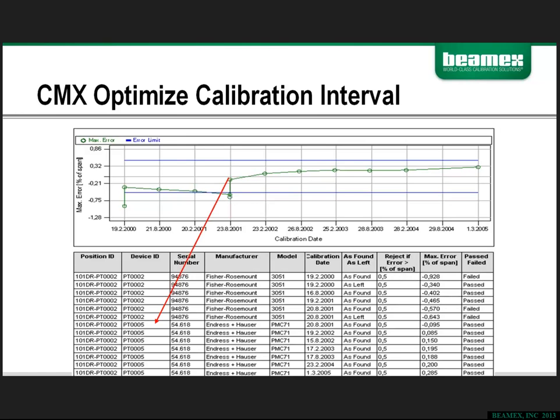and was subsequently replaced. So when it was replaced, if you see, based on the two blue lines, the unit that was brought in, when it was calibrated, it was about as close to center as you can get. And that's really what you're looking for, is the mean average of that particular span. If you're in the middle, then you have the benefit, if there is drift, that whether it be higher or lower than nominal, you're going to at least be within tolerance for a specific period of time. So the red block identifies that once it was replaced, we saw all passing performance, very center line, very minimal drift.